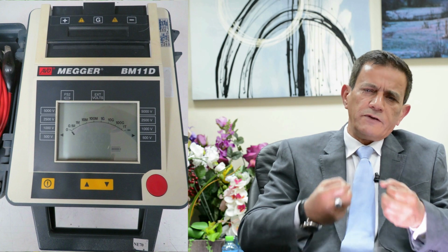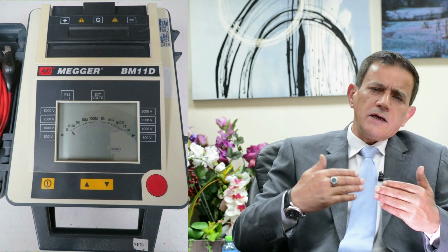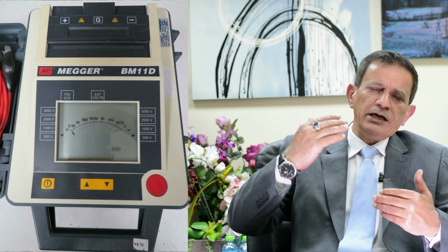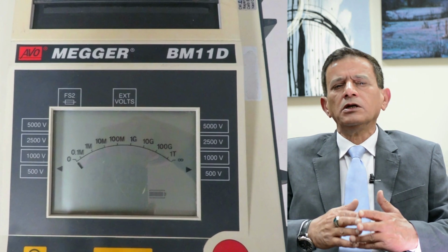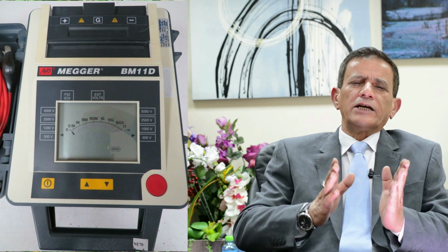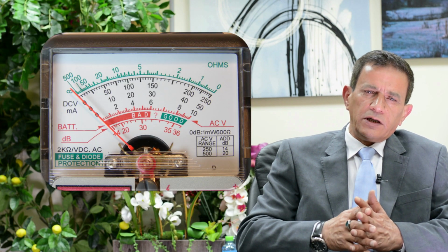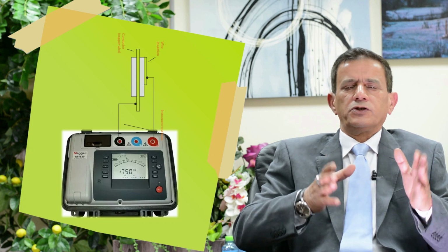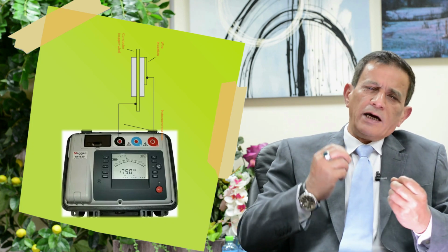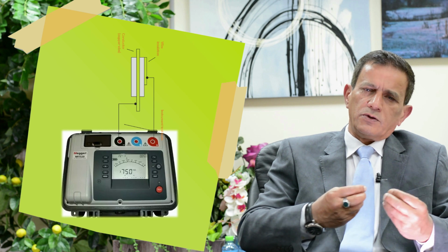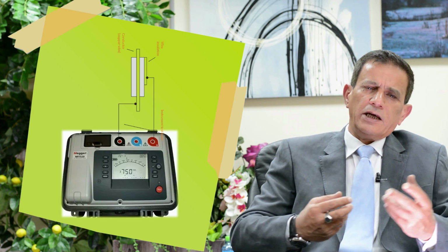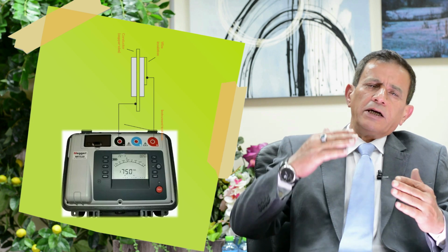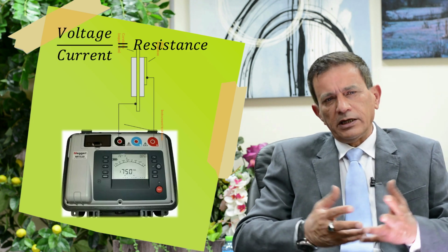For the megger, the name is derived from mega ohm meter, since the insulation resistance is supposed to be high, in the range of mega or even giga ohm, so this device has a larger range than the ohm meter found in the multimeter. And this test is based mainly on the simple Ohm's law. This meter will inject voltage in the insulation material, and by measuring the current, which will be in the range of maybe micro or milliamps or even nanoamps, by dividing the voltage by the current, we can get the resistance of the insulation.